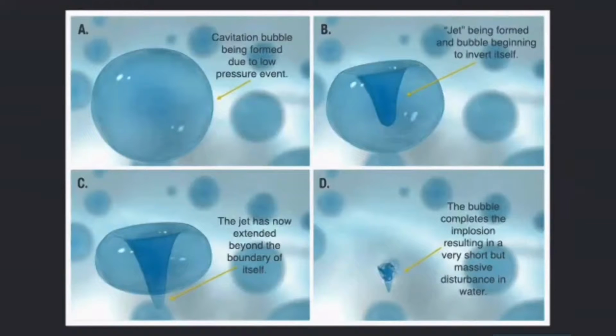Okay, so if you look up in A, these negative air pressure moments that I mentioned a moment ago, when these cycles of sound are at the bottom of their cycle, you have these low pressure events that occur, and a bubble is formed. A gaseous bubble occurs in the solution that otherwise a bubble shouldn't or couldn't exist.